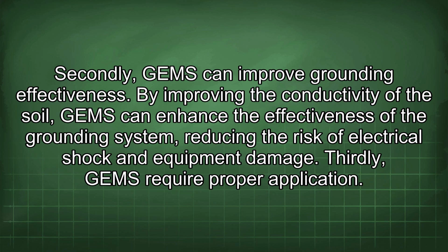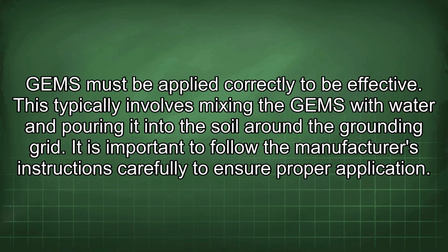Secondly, GEMs can improve grounding effectiveness. By improving the conductivity of the soil, GEMs can enhance the effectiveness of the grounding system, reducing the risk of electrical shock and equipment damage. Thirdly, GEMs require proper application. GEMs must be applied correctly to be effective. This typically involves mixing the GEMs with water and pouring it into the soil around the grounding grid. It is important to follow the manufacturer's instructions carefully to ensure proper application.